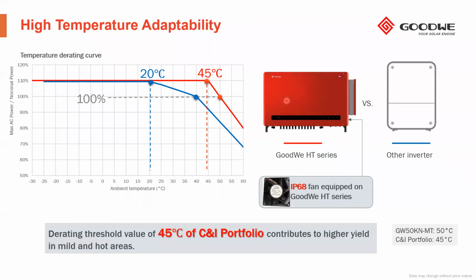So the way that the inverter manufacturer has to control and to keep the IGBTs in a good shape is by means of controlling the input of the inverter. And that's why we need to sensorize the inverter, as we do, to monitor the inner temperature, and that means that we can estimate the heat inside of the inverter. Then by means of this algorithm, the derating, we can control the input. There is a temperature threshold that every inverter manufacturer defines for when the inverter has to change the operating input of the PV array, and therefore reduce the output power.